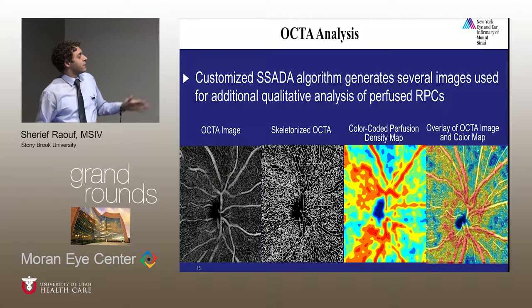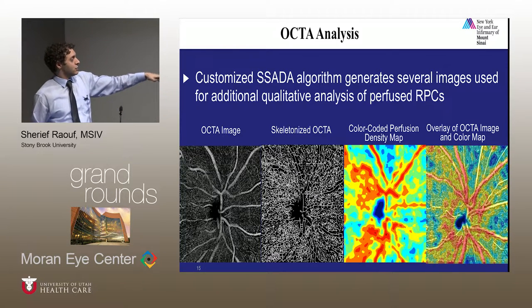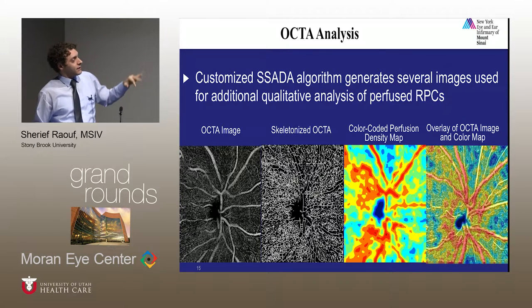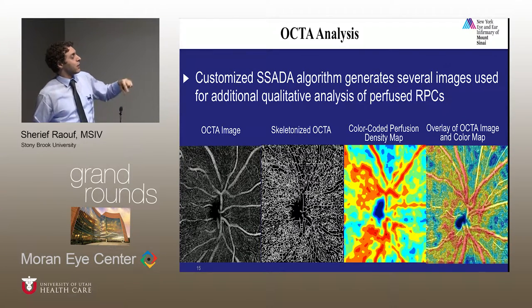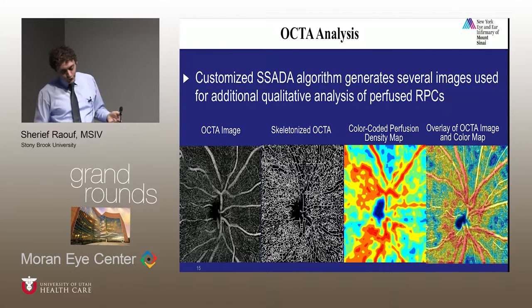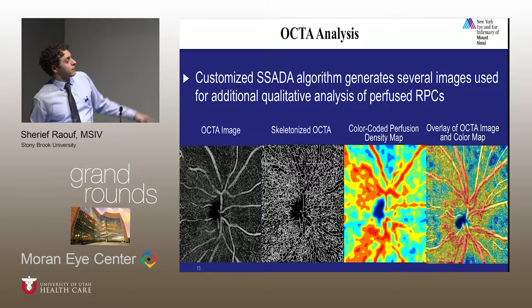A bit about image processing. On the left is the standard OCTA image. Next is a skeletonized OCTA, which assigns every vessel a uniform one-unit width regardless of its actual width. This allows better visualization of areas of dropout and prevents overestimating the effect of large vessels on the perfused vessel density calculation. The final two maps are color maps where each pixel is assigned a color based on local density: greater than 50% perfusion is red, zero is blue, and intermediate colors are assigned accordingly. The overlay of the two can be quite illuminating.